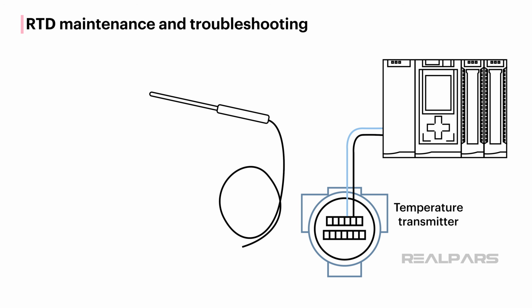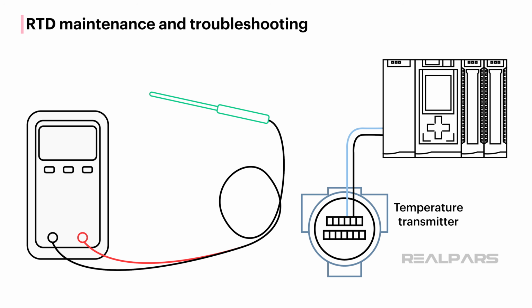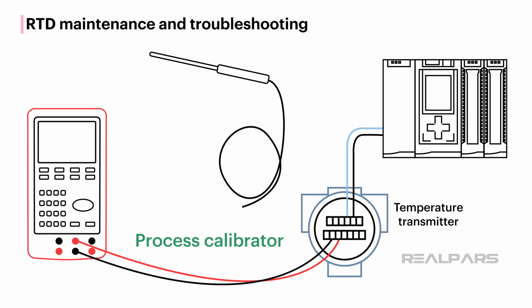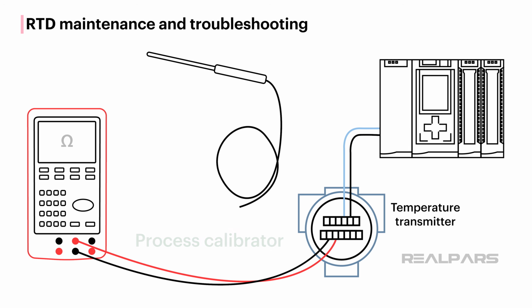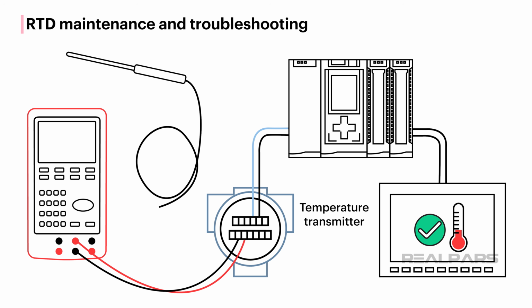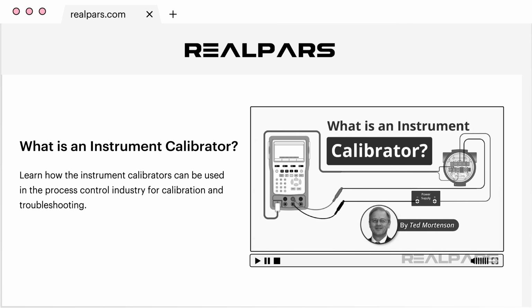You can perform a very quick and simple test by isolating the RTD and connecting an ohm meter across it. The RTD will read a finite resistance value of approximately 110 ohms to 115 ohms, depending on the ambient temperature. The best way to isolate the problem is by using a process calibrator to replace the RTD in the measurement circuit. The process calibrator can simulate the RTD by producing a resistance and applying that resistance to the transmitter. In our illustration, if the HMI indicates the expected temperature, the problem is with the RTD. If you want to know more about process calibrators, check out our video called What is an Instrument Calibrator?